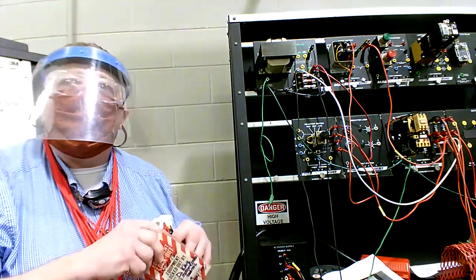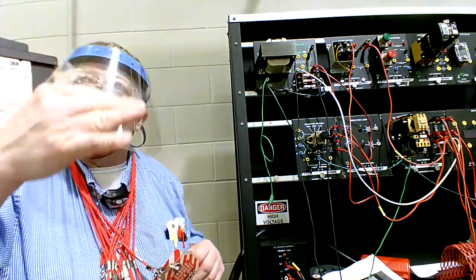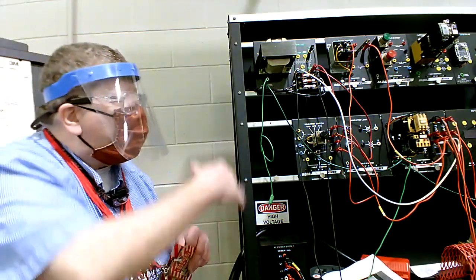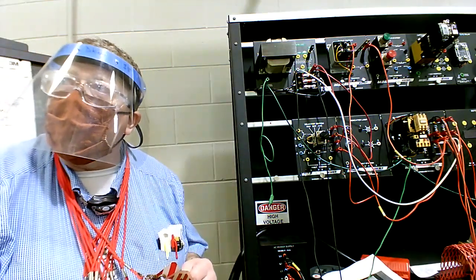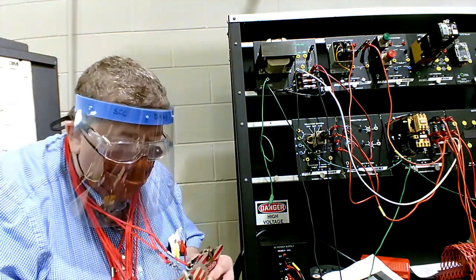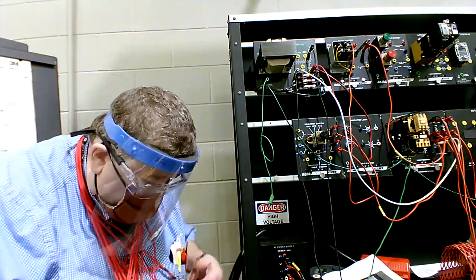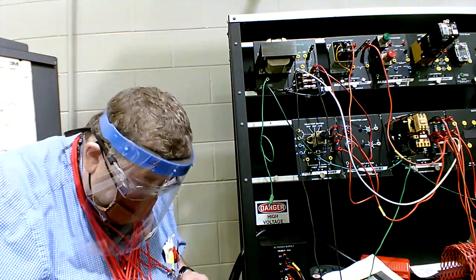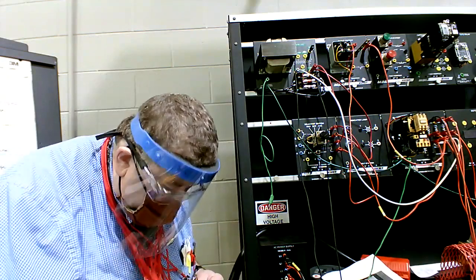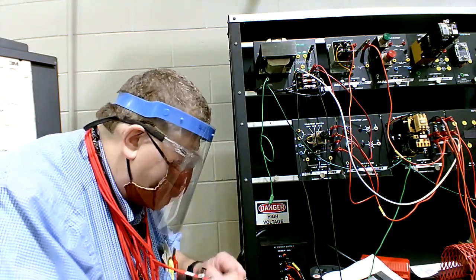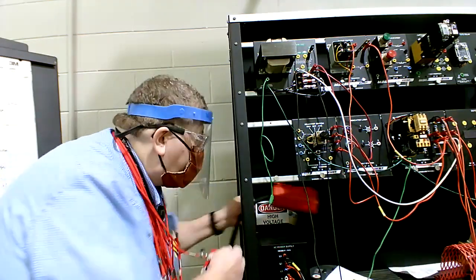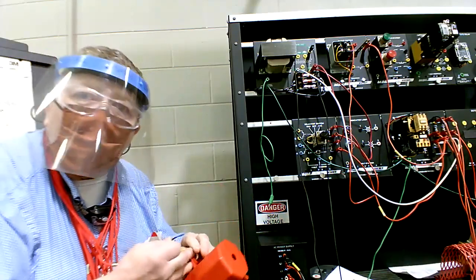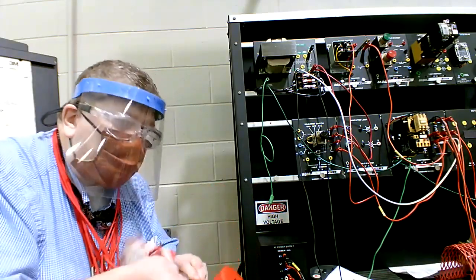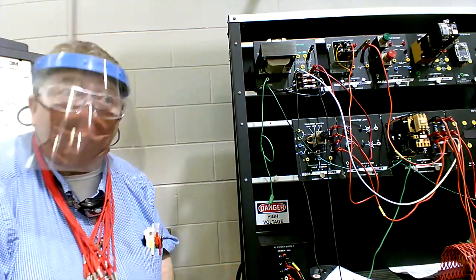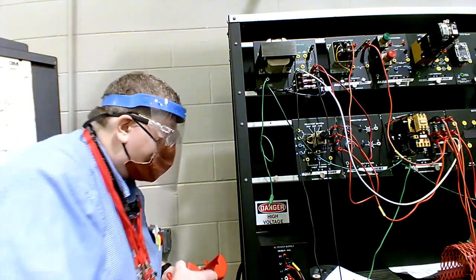And the reading that you get will actually be very unpredictable. I've seen reads as high as 140 volts that way. And then on this one, it actually reads like about 30 volts to ground. If you don't ground neutral, it'll read about 30 volts. It's something that you don't know what the number is going to be. But it's definitely something that we need to look at together as a group, and tell me if something's not making sense about what you're seeing, because you will definitely run into this out there in the industry. You will run into this issue.